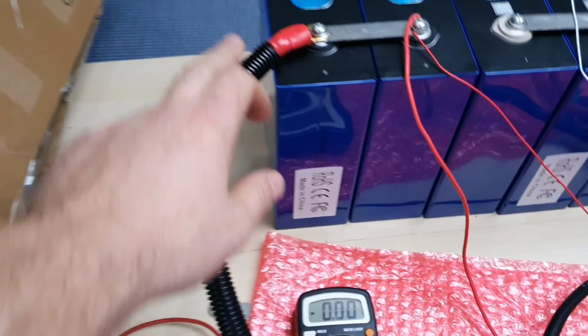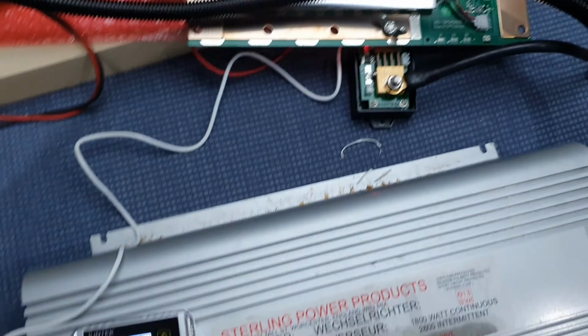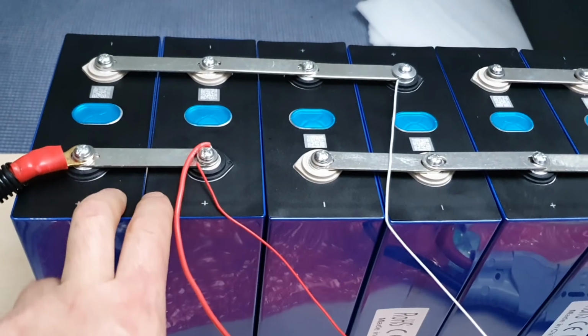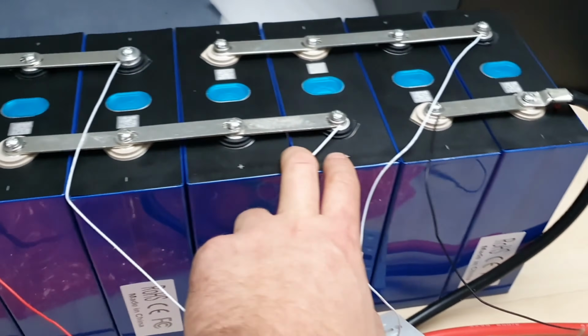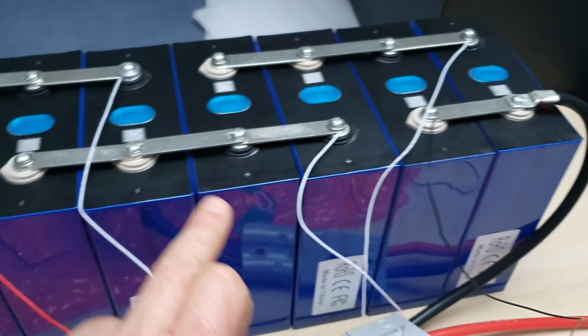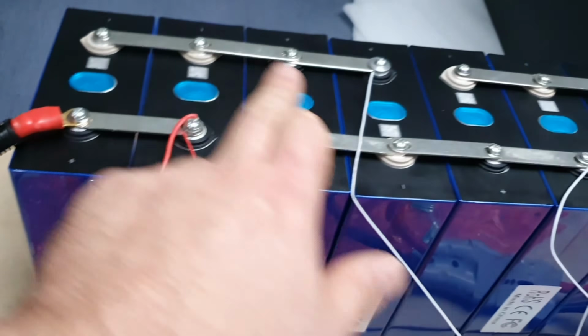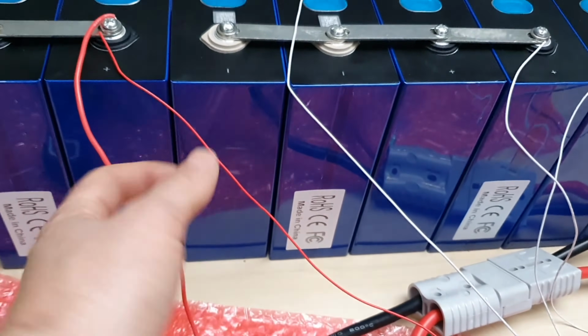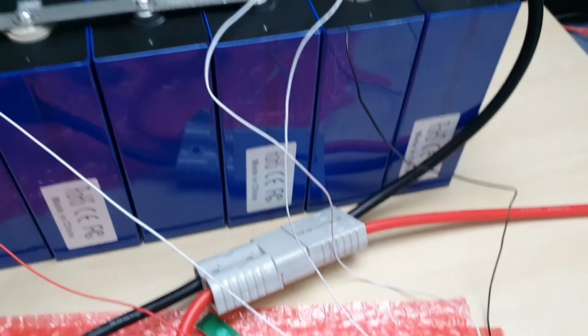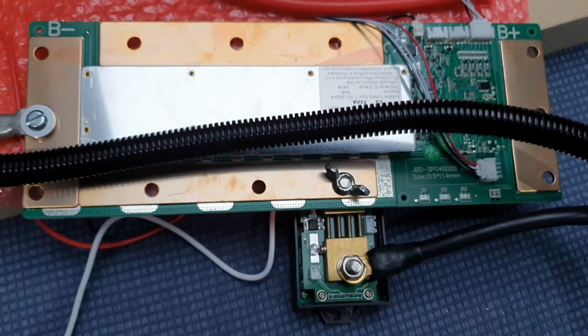We've got the positive out of the battery here going directly into the inverter. The packs are wired in series, so there's a parallel pair, parallel pair, parallel pair, parallel pair, and then it's wired in series for each parallel pair. You can see the balance wires coming off down here to the BMS.